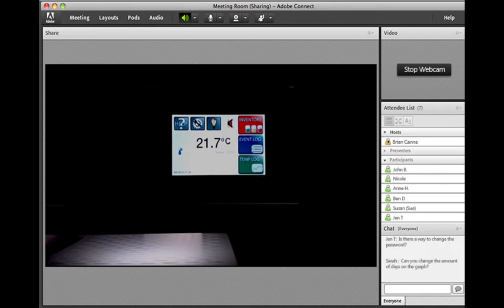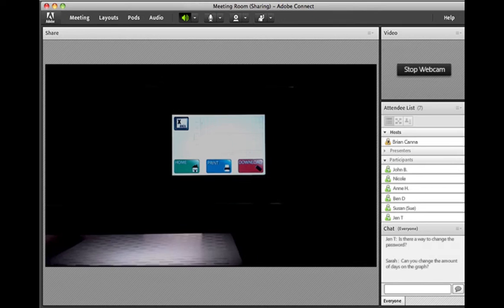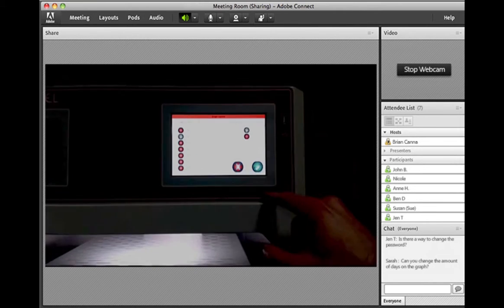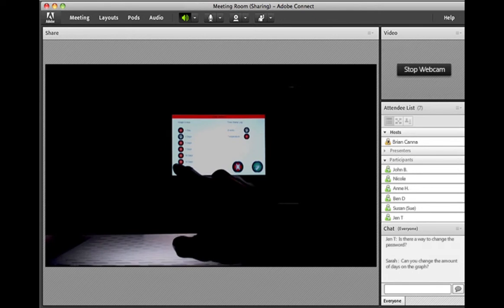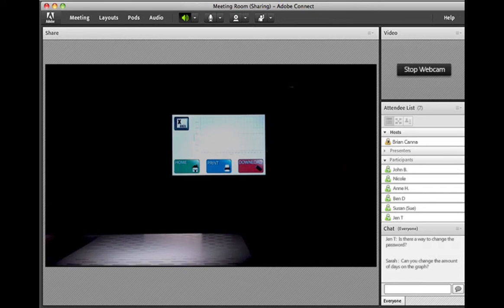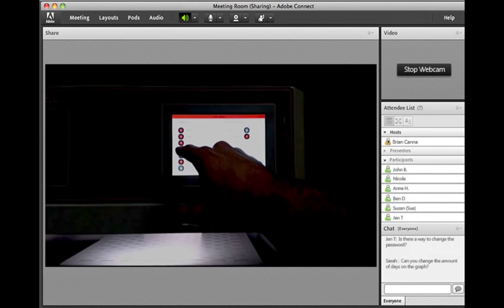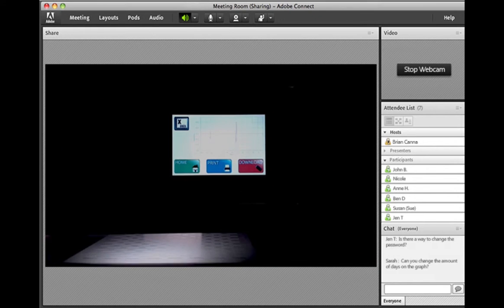It looks like we have a question from Sarah about changing the x-axis on the temperature. So yeah, I set it to 3 days just so we didn't print out tons of information on our print. But if you go to the x-axis, you can actually get 30 days of data on the graph and on the printer. So if we go back into here, you can see we've got some data up until 324 hours ago, but it looks like the unit was turned off back here and turned on. So let's look at 7 days worth of data, which is what someone typically might be looking at. And as you can see, we have our low temperatures over here on the right side because we were testing all those things today.